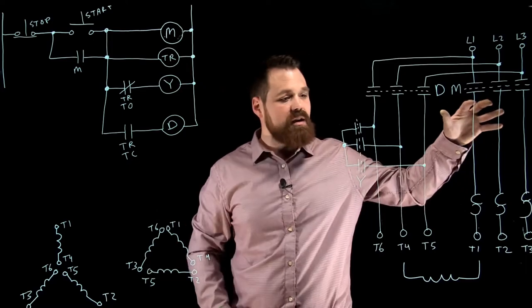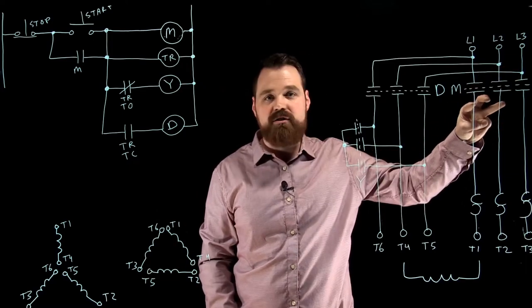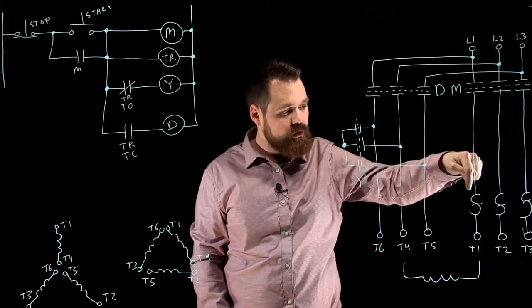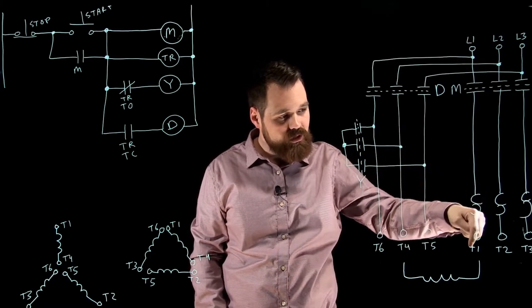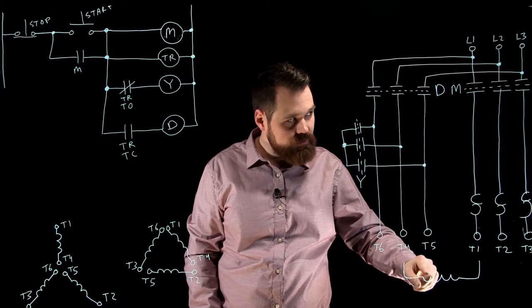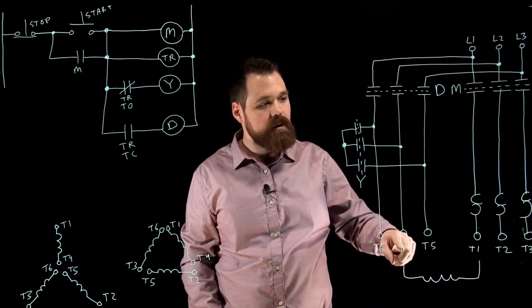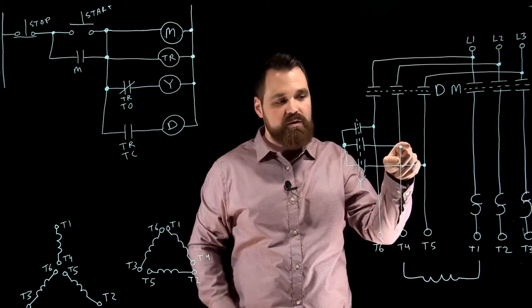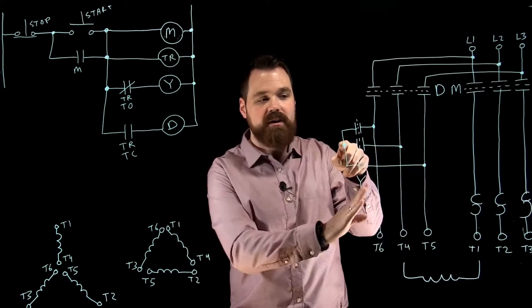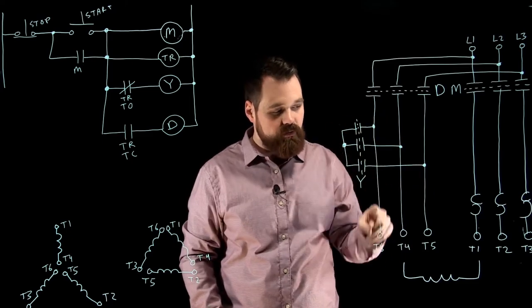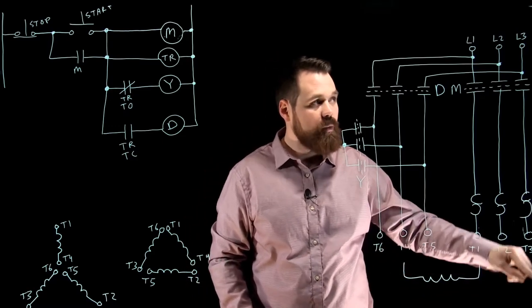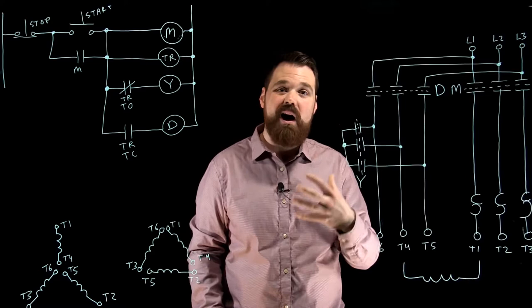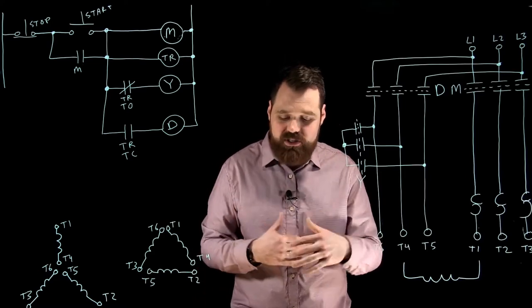What that means is I'm going to have these three contacts close, and I have current flowing through line 1 through my set of overloads, through my coil T1 through T4, and then back up to here. These sets of contacts are open, so what I do is I go through this Y point and then back over through T6, back up T3, and I'm basically starting in that Y formation, so I see that reduced current.